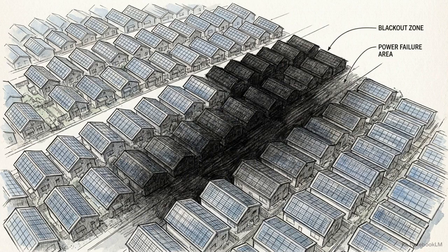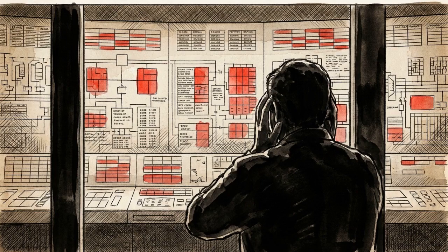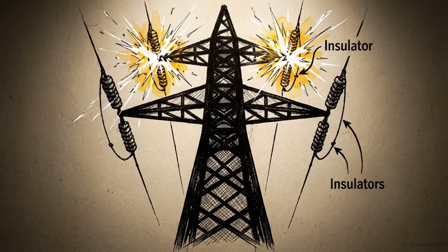Simultaneously, an exacerbating factor occurred in the low-voltage distribution grids. Thousands of sub-1 megawatt rooftop solar PV inverters also began tripping offline due to localized overvoltage. These localized rooftop trips wildly altered the power flows between the transmission and distribution networks, further blinding dispatchers to the full scope of the destabilization. In a 21-second self-sustaining death spiral, automated overvoltage protections actively destroyed the grid's remaining ability to regulate its own voltage.